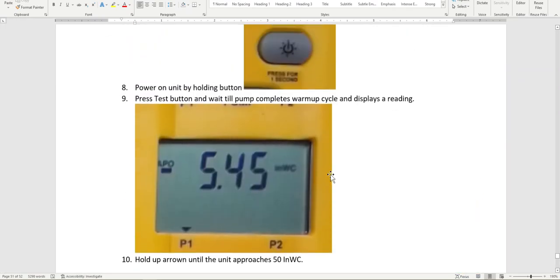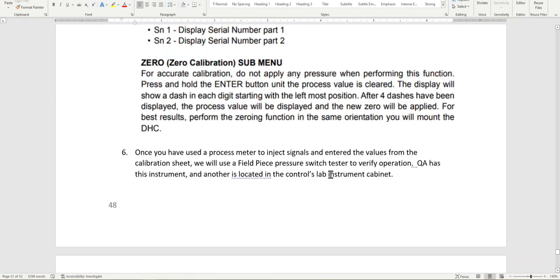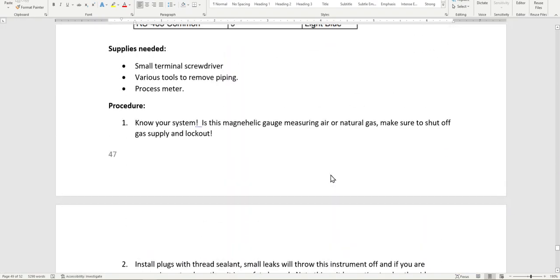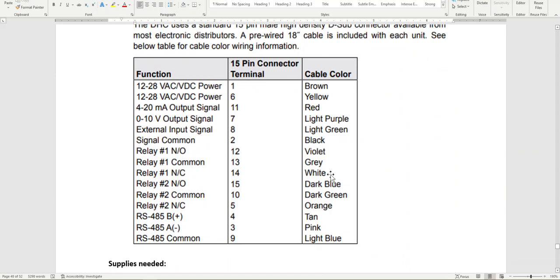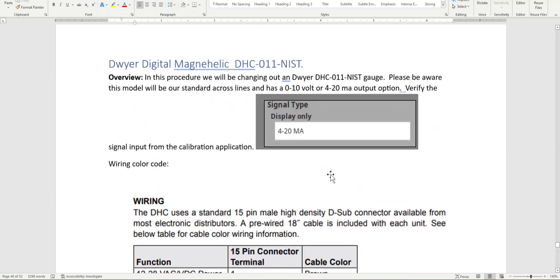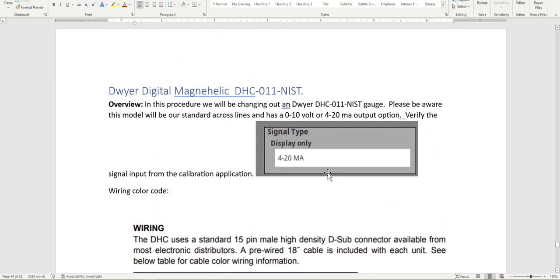Let's go through here. So I'll show you where we're at in this video. First of all, you're going to have to know the signal type display listed in your calibration app. We're ordering one meter. This has a 0 to 10 volt or a 4 to 20 milliamp output. So you'll have to look and see how it's supposed to be wired.